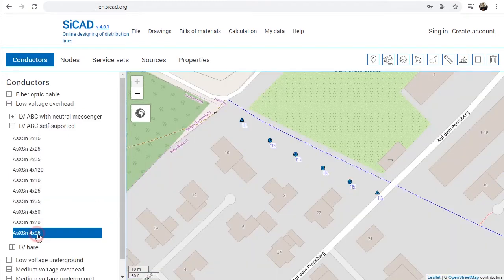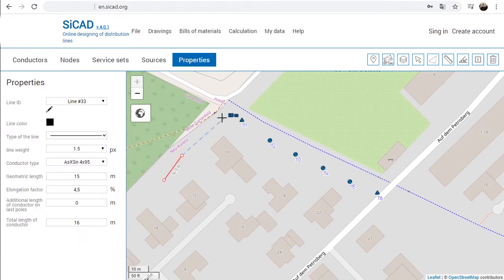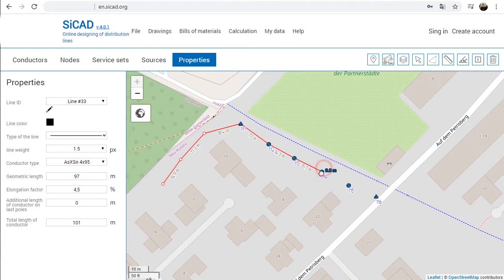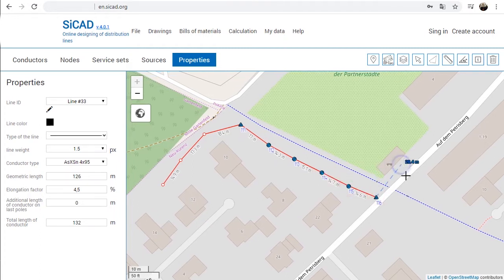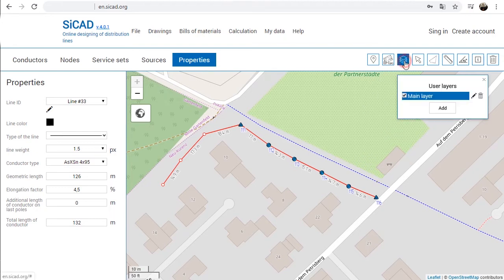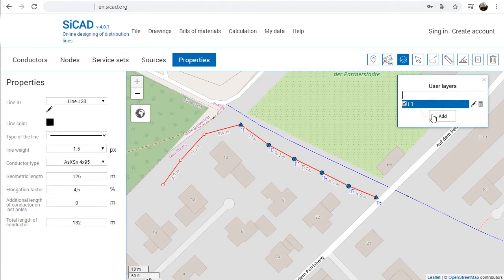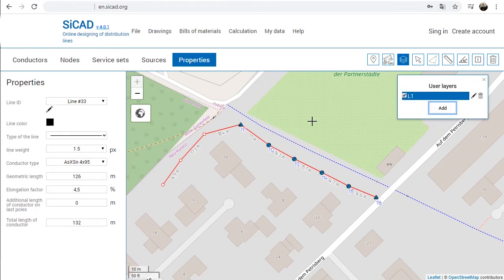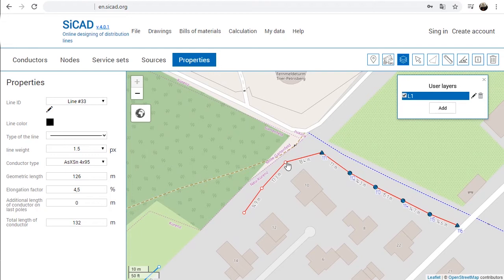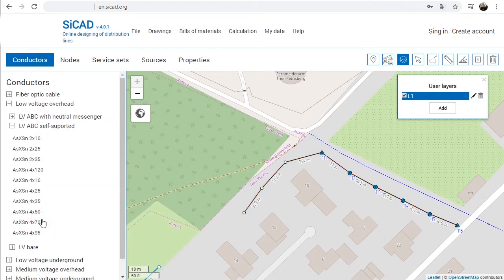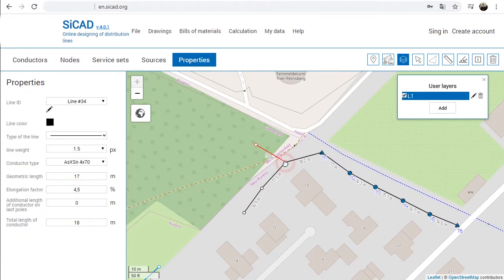The line can be drawn both ways: directly clicking on the map, or clicking on already placed nodes on the map. The lines are created in the active layer of the user layers toolbar. A newly drawn line can also be attached to a line already existing on the map if they are in the same layer. In this case, these lines will have a common point. When moving the common point, the attached lines also move with that point. Lines attached in a common layer are considered to be electrically connected.